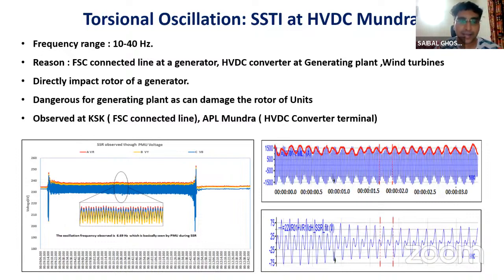So here it is a very high frequency range, and it will be difficult to observe this in PMU. It will be observed in PMU, but its frequency may not be clearly indicated, because PMU sampling rates are limited. So it will be more clearly visible in the disturbance recorder, where the sampling rates are higher.